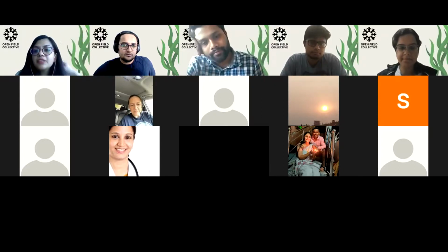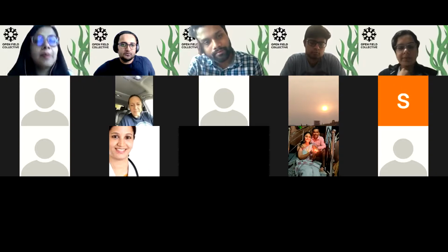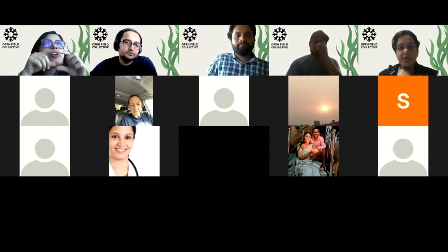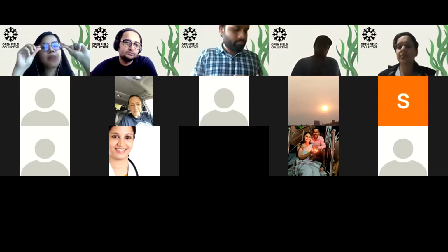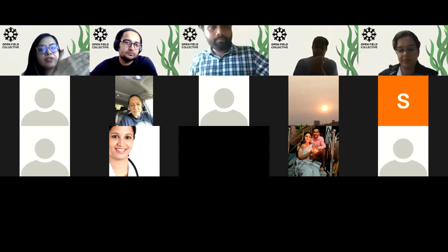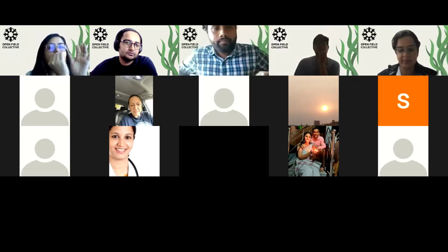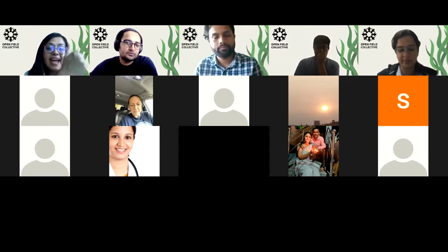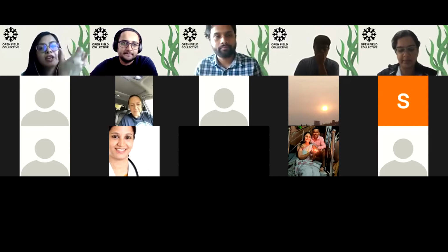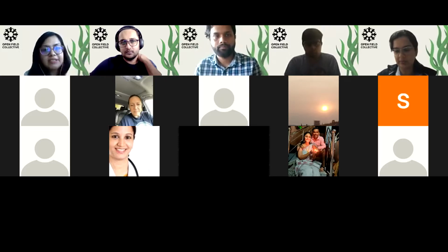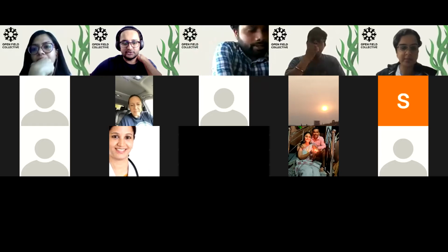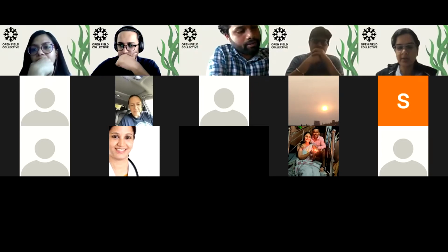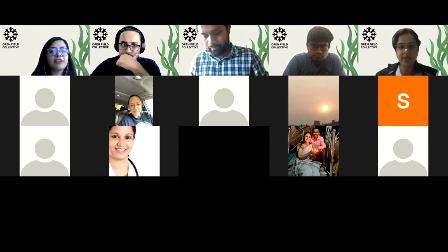So Dr. Vasavi said she tried some of the permanent slides from the lab and it's not clear with the Foldscope. If you want, we can sit with you as well. But one of the few things which often is an issue when focusing with Foldscope is to make sure that you're on the right side with respect to the sample, like you're not viewing it from the side of the microscope slide, but more towards the cover slip. So the cover slip should be closer to the lens. Maybe Iqbal, can you show with the Foldscope where the slide should be? Okay, so she's saying that was placed properly.